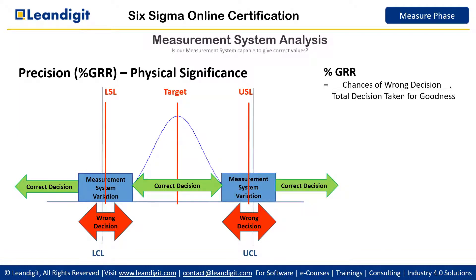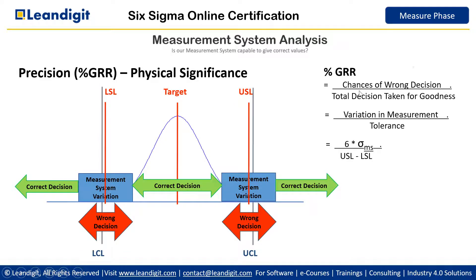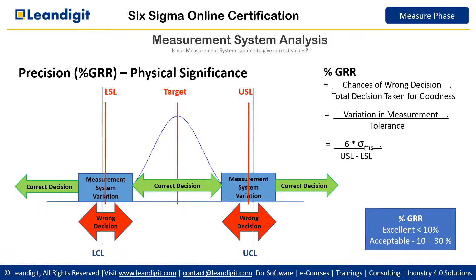Percentage GRR represents the chances of a wrong decision — that is, the measurement system variation — divided by the total tolerance for goodness, which is the specification width. Variation in measurement is six times the measurement system standard deviation, and tolerance is USL minus LSL. This ratio is called percentage GRR. If this value is less than 10%, we say our measurement system is excellent. If it is between 10% and 30%, it is acceptable. Beyond 30%, the measurement system must be rejected and improved.